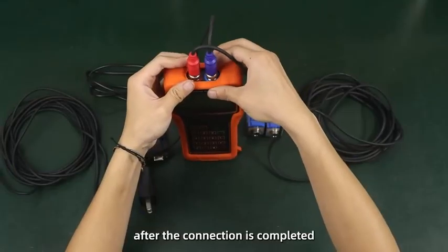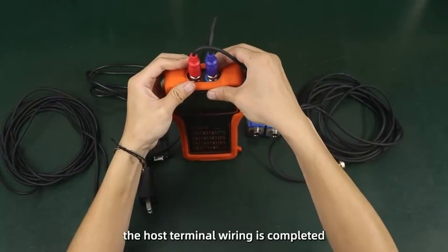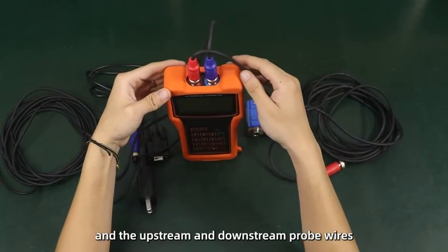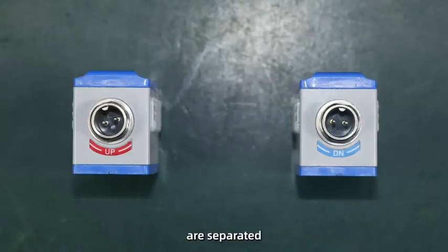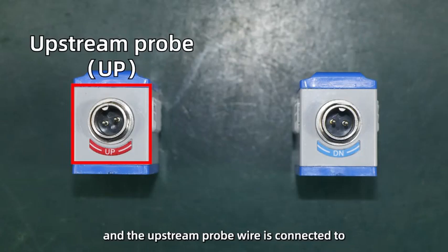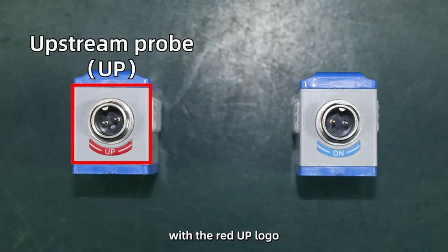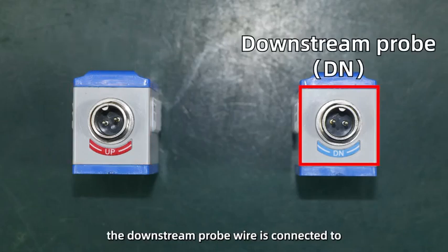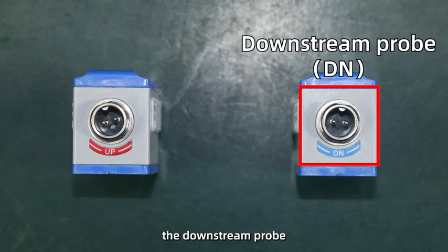After the connection is completed, the host terminal wiring is completed, and the upstream and downstream probe wires are separated and connected to the corresponding probes. And the upstream probe wire is connected to the upstream probe, that is, the cable with the red logo is connected to the probe with the red up logo. The downstream probe wire is connected to the downstream probe, that is, the cable marked with blue is connected to the probe marked with blue DN.